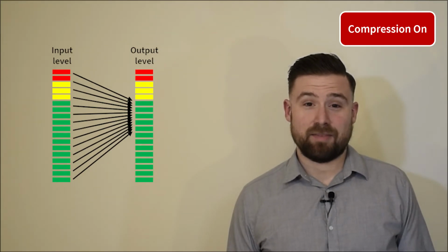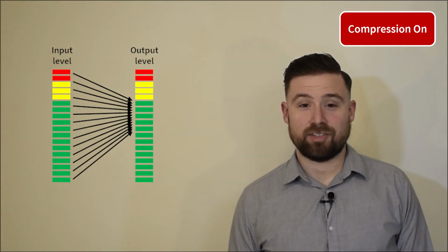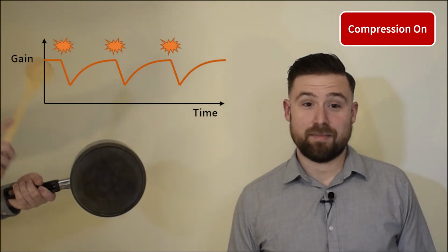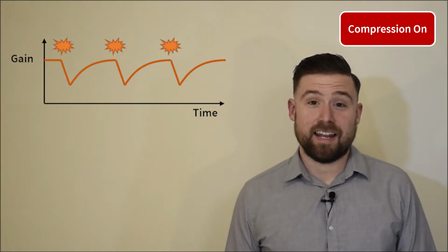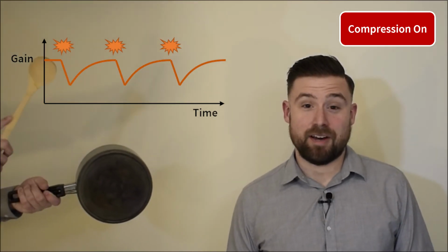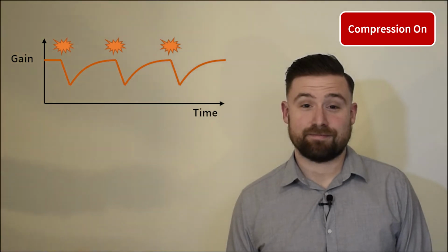Right now, you're hearing my voice with exaggerated dynamic range compression applied. This severe compression keeps the sound level close to constant. If there is a sudden loud sound, then the hearing aid will turn down the gain, meaning my voice will also get quieter. Let's hear that again, but this time, through the magic of pre-recorded presentations, you won't hear the pot, only my voice compressed as if the pot were there. My voice dips in and out, making it harder to understand even without the extra noise.